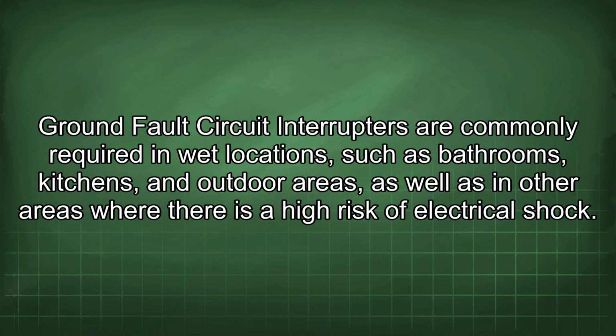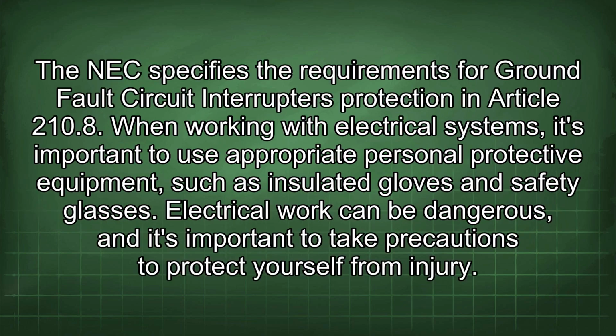Ground fault circuit interrupters are commonly required in wet locations such as bathrooms, kitchens, and outdoor areas, as well as in other areas where there is a high risk of electrical shock. The NEC specifies the requirements for ground fault circuit interrupter protection in Article 210.8.